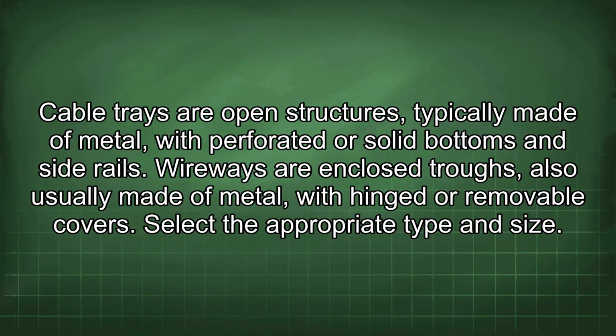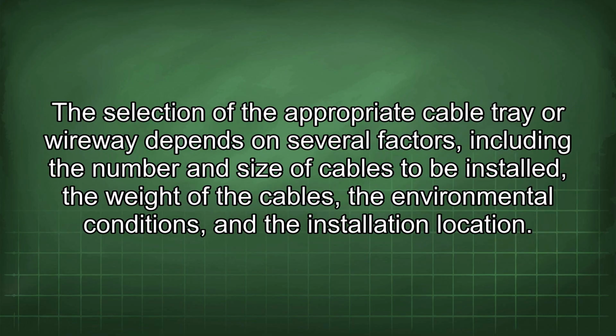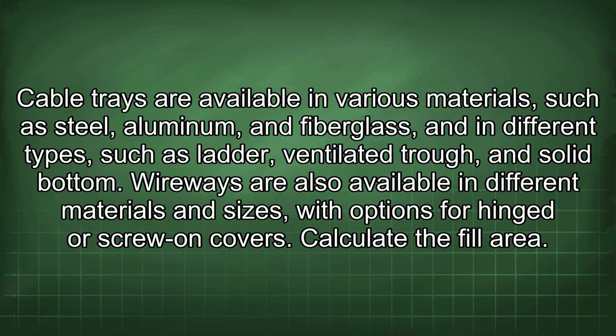Select the appropriate type and size. The selection of the appropriate cable tray or wireway depends on several factors, including the number and size of cables to be installed, the weight of the cables, the environmental conditions, and the installation location. Cable trays are available in various materials such as steel, aluminum, and fiberglass, and in different types such as ladder, ventilated trough, and solid bottom. Wireways are also available in different materials and sizes, with options for hinged or screw-on covers.